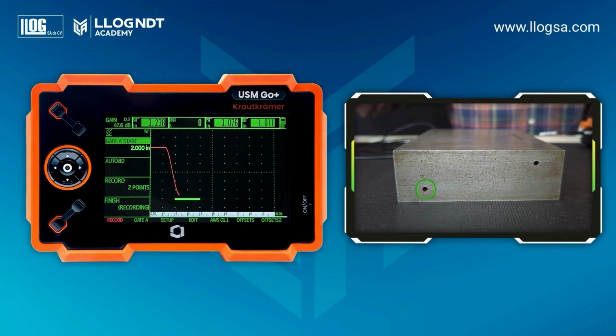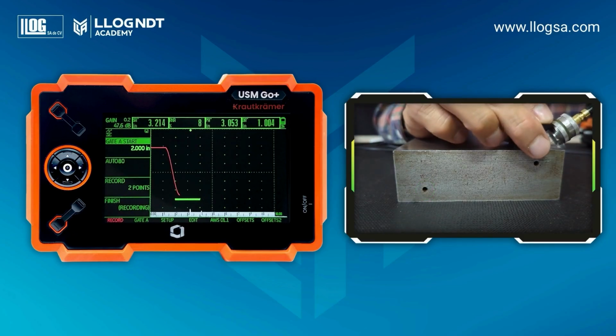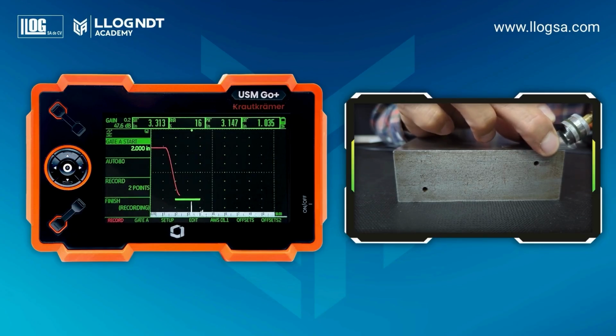To obtain the third point, place the transducer toward the hole located at 3/4 T. Search for the maximum amplitude by moving the transducer back and forth. Without changing the gain, press the right key again to save the third point.